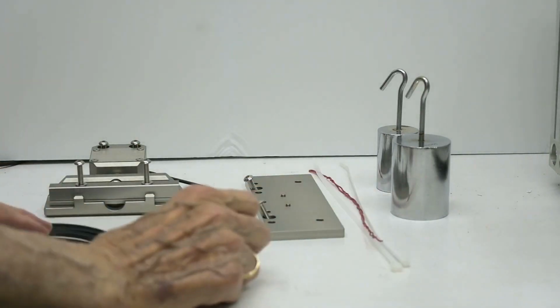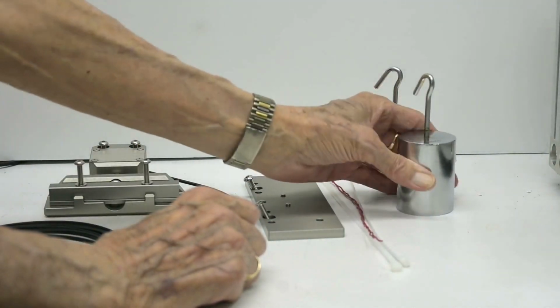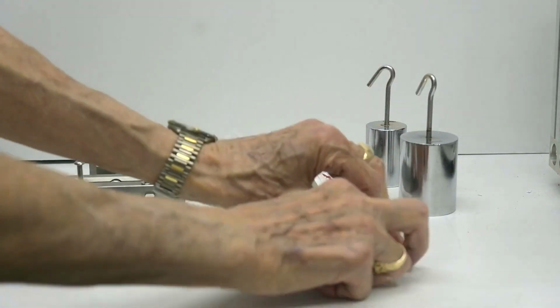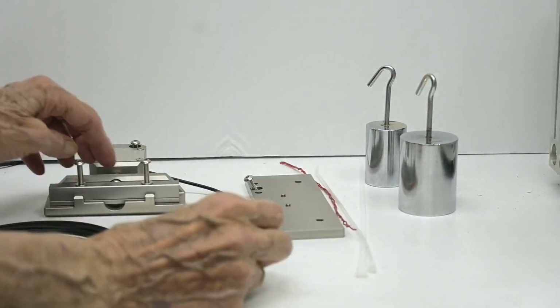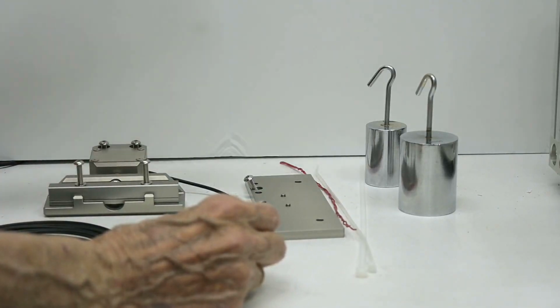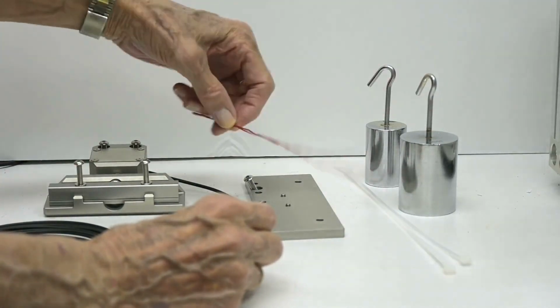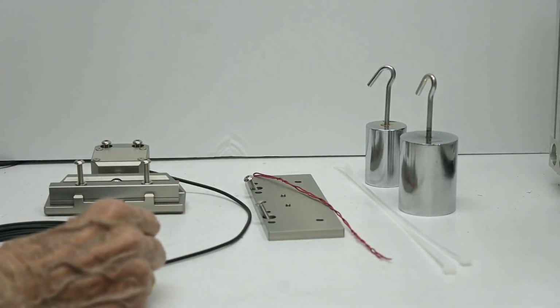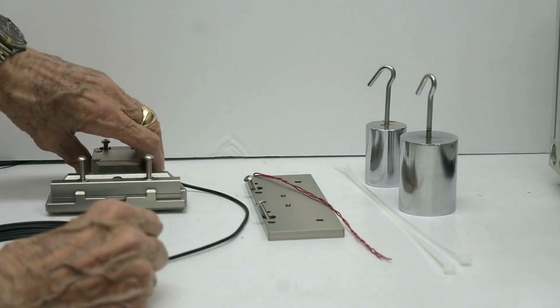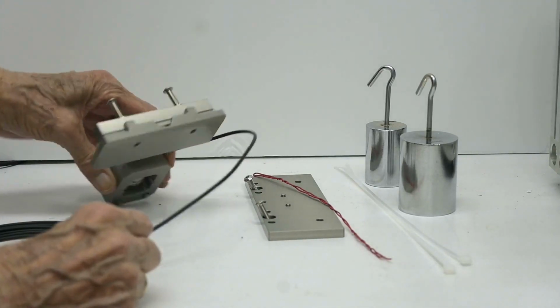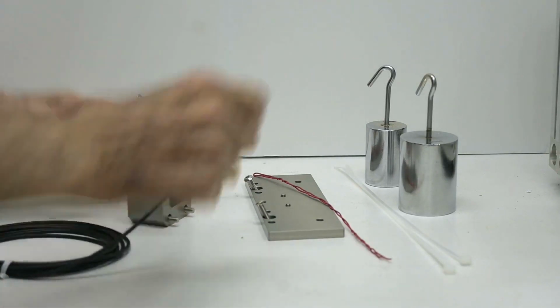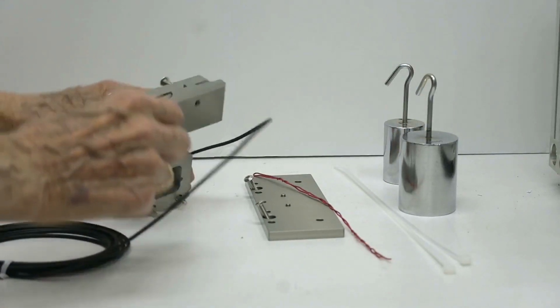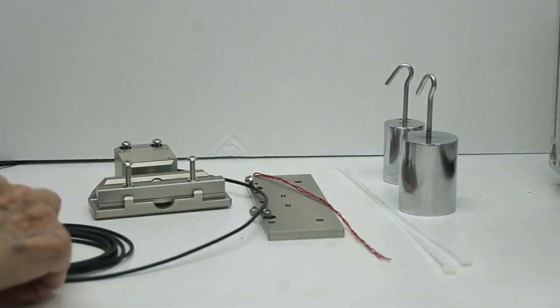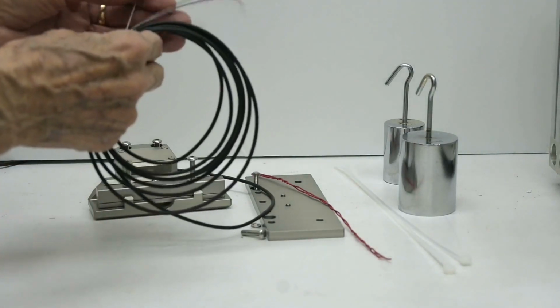I'm going to use these two weights for calibration, 1 kilogram and 1/2 kilogram. These two cable ties will be used to hang the load cell from the ceiling. I'm going to use this wire to hold the weights to the sample clamp when I am testing tension. To test compression, I will put the device on its end and put the weights on the other end. This is the wiring cable, 5 wires. I will show you later what to do with them.